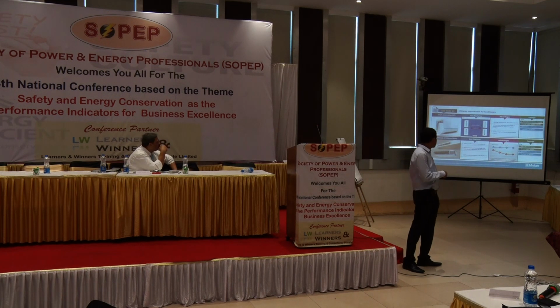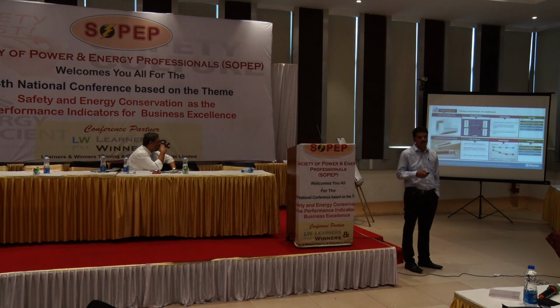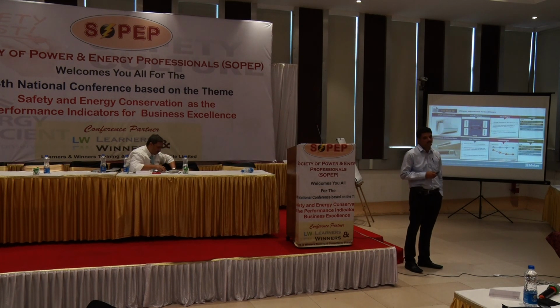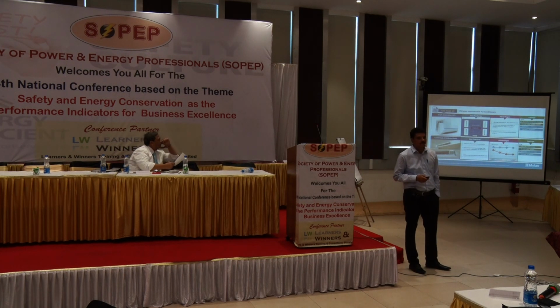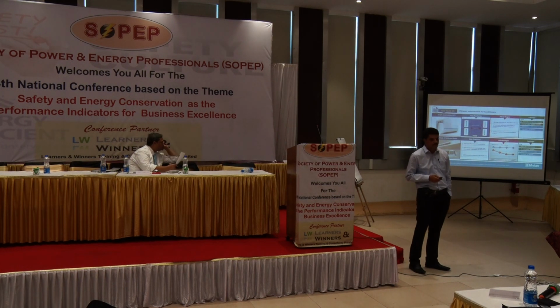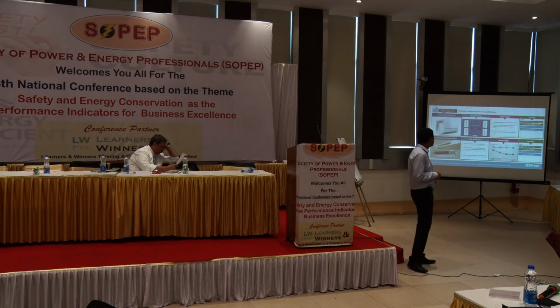So these are the small automations. Wherever there are admin blocks and central ACs, people will not be there and they cannot stop the central ACs. So wherever possible, we have replaced them with split ACs and removed the central AC to save energy. In canteens and all, we have arranged one small automation with the PLC. As per canteen timings, ACs automatically start and stop. With this, the small investment has payback of 8 months and 11 months.